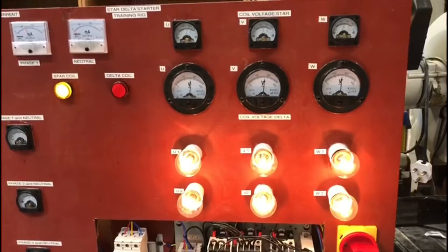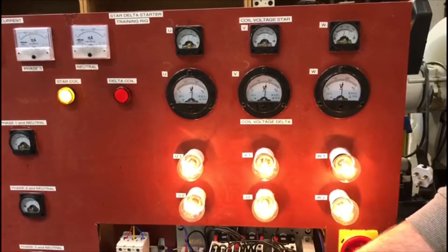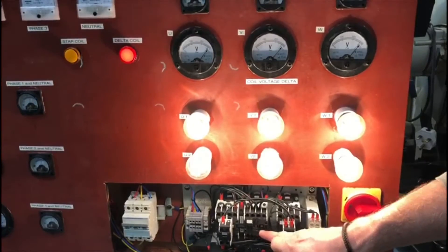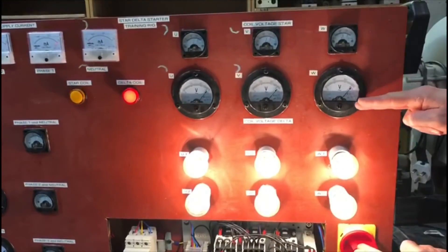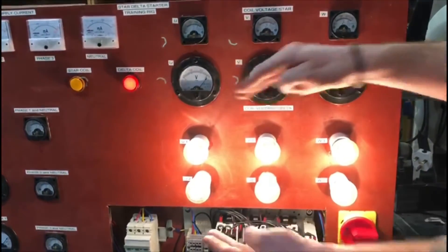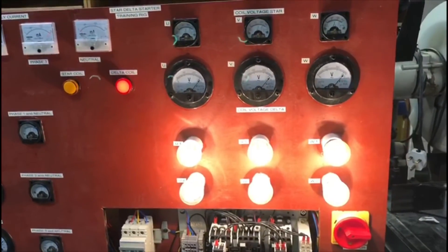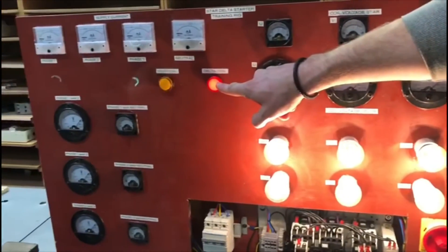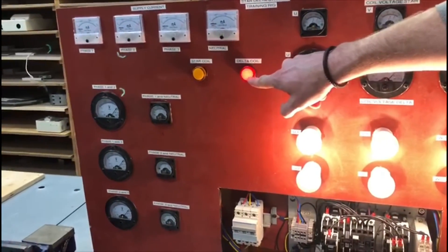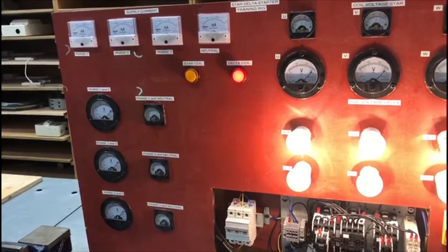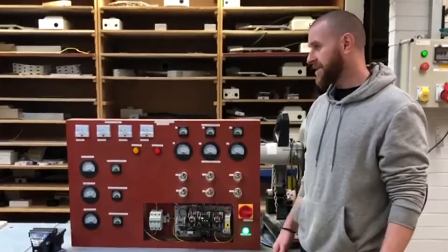This will change over. This contact will pull out and this contact will pull in, and you can see that pulling in there. And now, 400 volts is appearing across both of these pairs of lamps, and you can see they're working much brighter. And also, I don't know if you saw that, we've now got the delta lights lit up. And before, the star one was lit up.